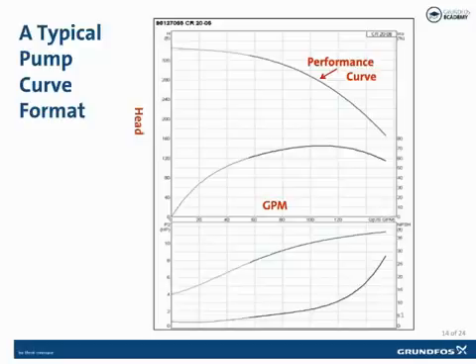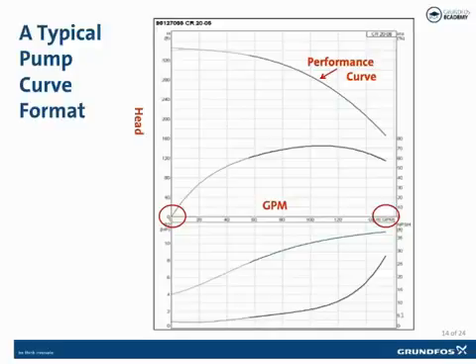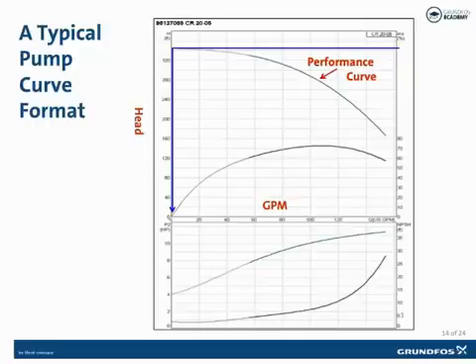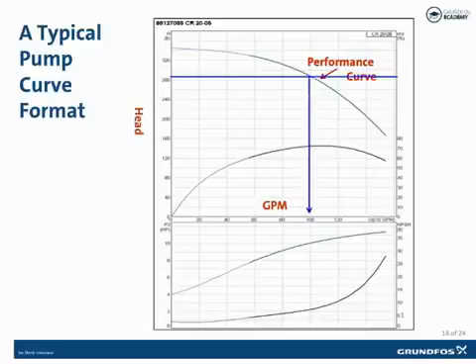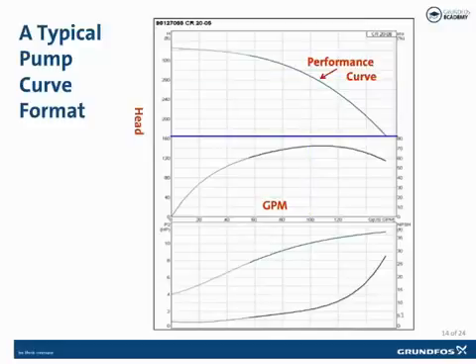The pump listed here can produce anywhere from 0 to just over 150 gallons per minute depending on the system where it's installed. For instance, if this pump were put in a system with 343 feet of head, the pump would produce 0 gallons per minute — this point is also known as shut-off head or deadheading the pump. If put in a system with approximately 290 feet of head, the pump would produce 100 gallons per minute. At approximately 170 feet of head, it would produce its maximum flow of just over 150 gallons per minute — this point is known as run-out, and there is a risk of cavitation when operating pumps at this point.